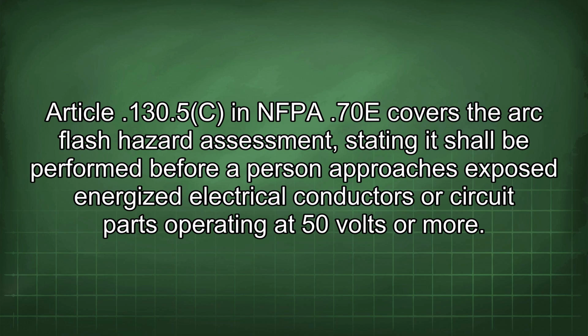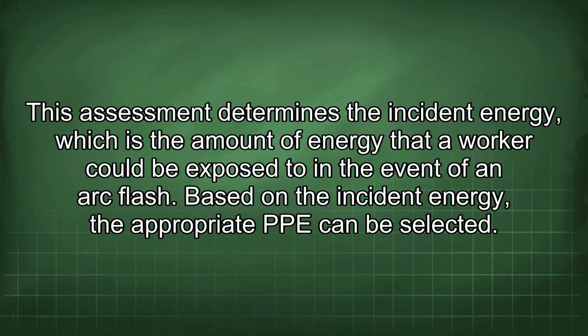Article 130.5(C) in NFPA 70E covers the arc flash hazard assessment, stating it shall be performed before a person approaches exposed energized electrical conductors or circuit parts operating at 50 volts or more. This assessment determines the incident energy, which is the amount of energy that a worker could be exposed to in the event of an arc flash. Based on the incident energy, the appropriate PPE can be selected.